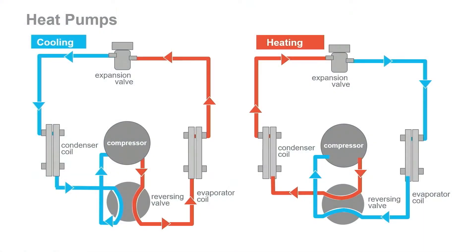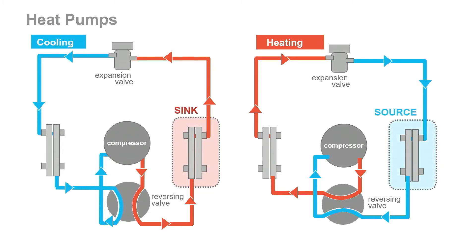In simple terms, a heat pump is a unit that contains a reversing valve in the refrigeration circuiting, which allows the evaporator and condenser to switch roles. When we look at heat pump heat exchangers, we use the terms source and sink instead of evaporator and condenser to describe where we are either absorbing energy from or rejecting energy to. Because of the switching of modes, these units can be considered reversible. Heat pumps can come in a wide range of sizes and are available in water source and air source versions.